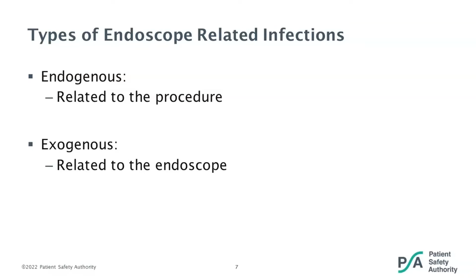So contributing factors for contamination, there's lots of literature out there to demonstrate failures in processes related to endoscopes. Moisture, retained debris. This retained debris could be proteinaceous material, stents, balloons, cleaning brushes, and other material. Scope damage, and this could be related to the shelf life of that device. How long has it been in service? How has it been maintained? Is there a breakdown within the scope itself that may warrant it coming to the end of use?